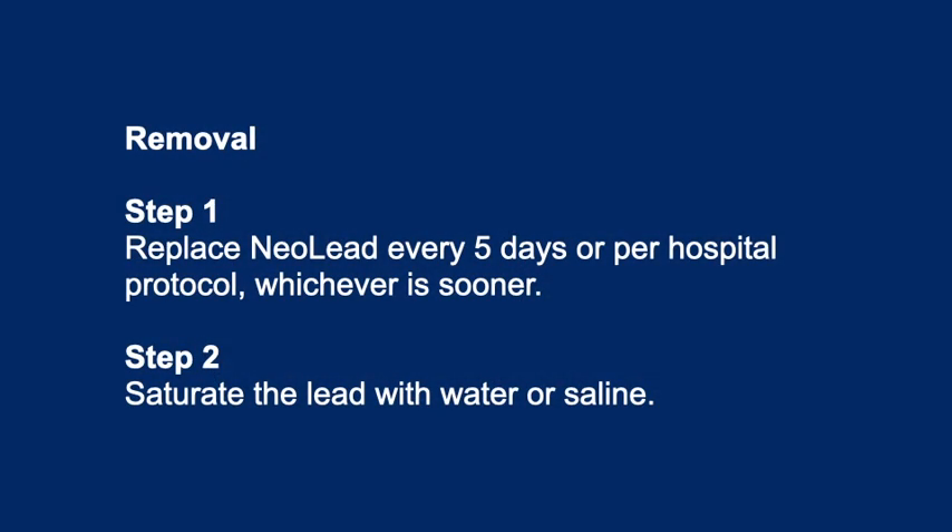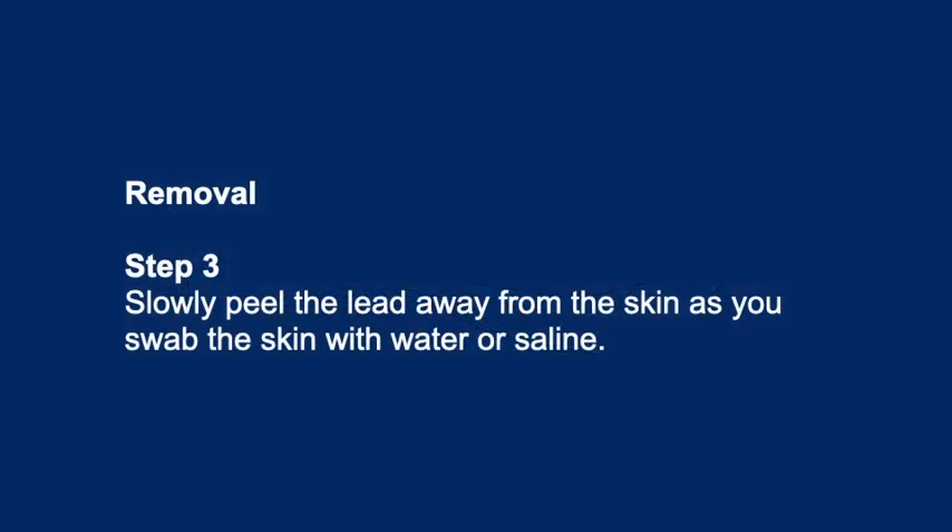Removal Step 1: Replace NeoLead every 5 days, or per hospital protocol, whichever is sooner. Step 2: Saturate the lead with water or saline. Step 3: Slowly peel the lead away from the skin as you swab the skin with water or saline.